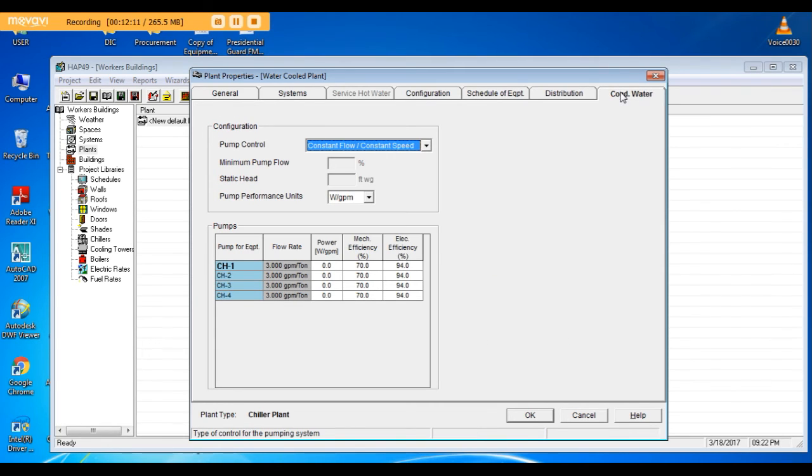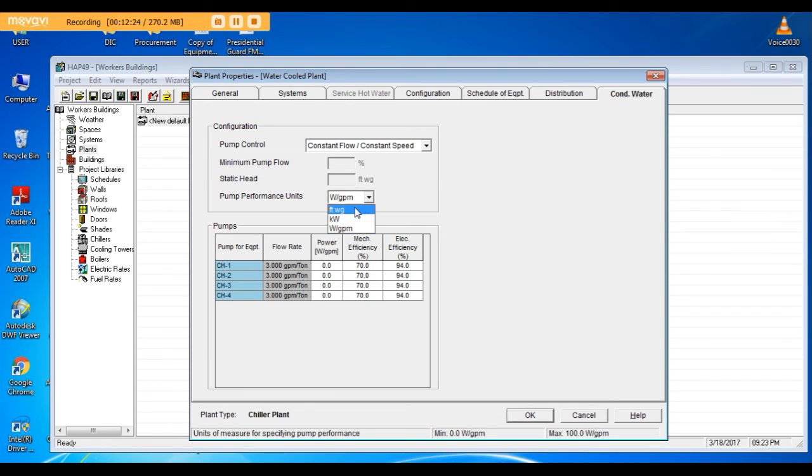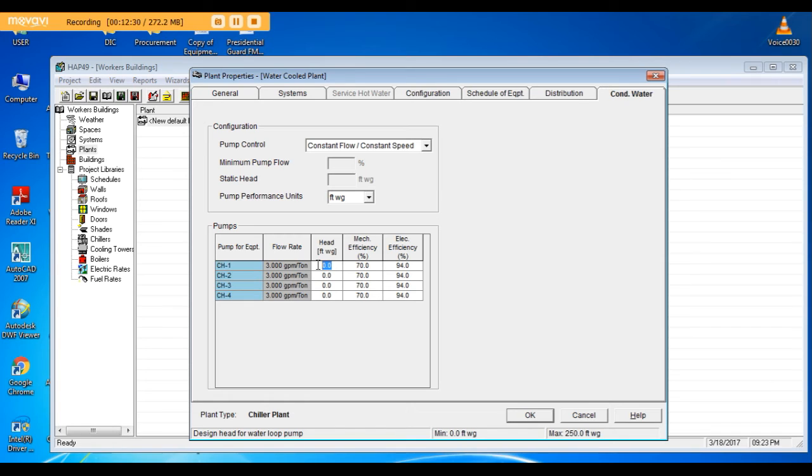Condenser water: constant speed pumps I need it. 3 GPM per ton. The head of the condenser pump, I will change it here to feet. The head required for the condenser pump is the static head from the condenser pump to the cooling tower plus the friction losses. In our project it is 100 feet.